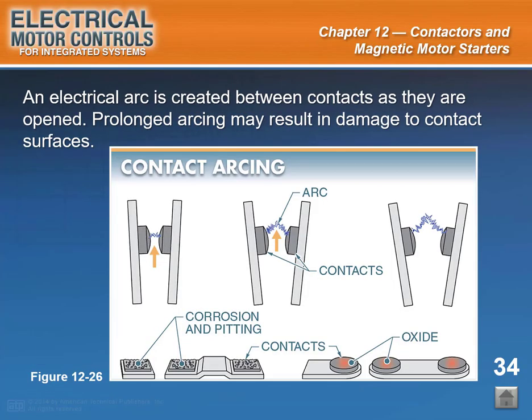Slide caption: an electrical arc is created between contacts as they are opened. Prolonged arcing may result in damage to contact surfaces. See Figure 12-26. A short time period, often just a few thousandths of a second, exists when a set of contacts is opened under load. During this time, the contacts are neither fully in touch with each other nor completely separated. End of slide 34. Start of slide 35.